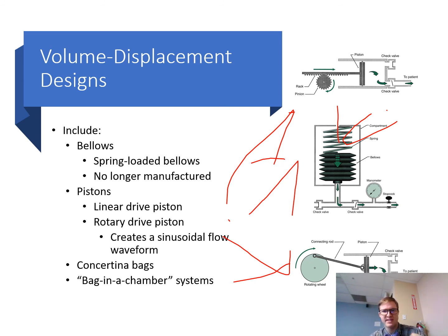to drive pistons. So incorporating a rolling seal or using low resistance materials has helped eliminate the friction that occurred with a lot of these devices. They would overheat. So they developed even better materials from those.